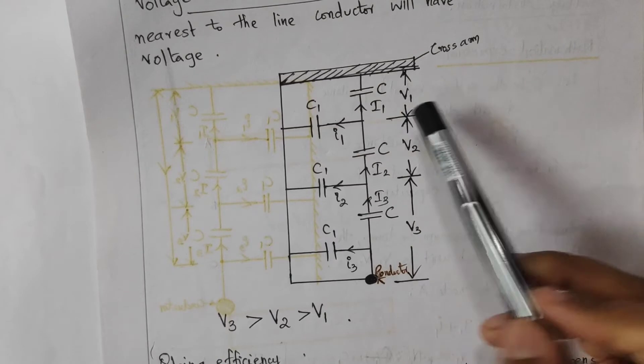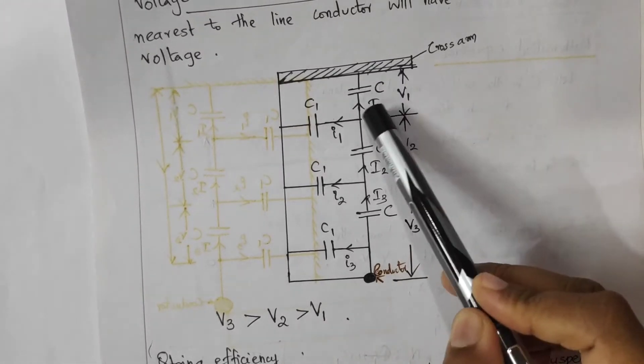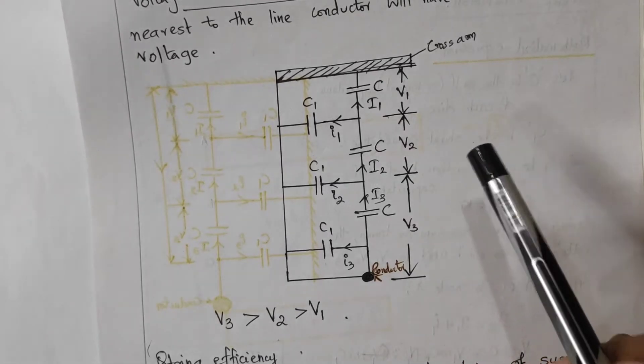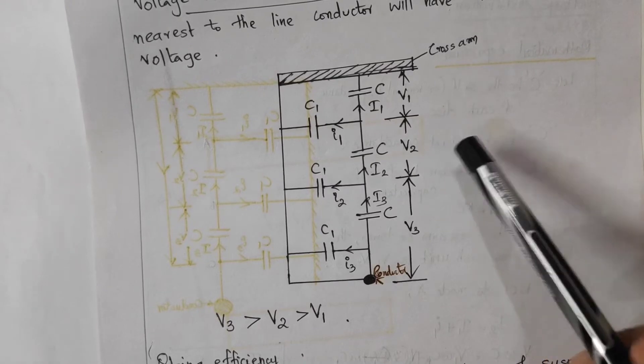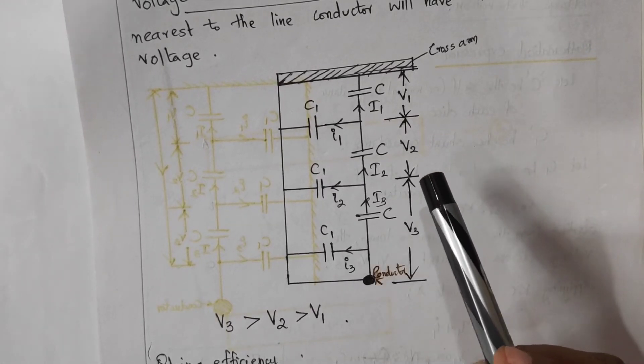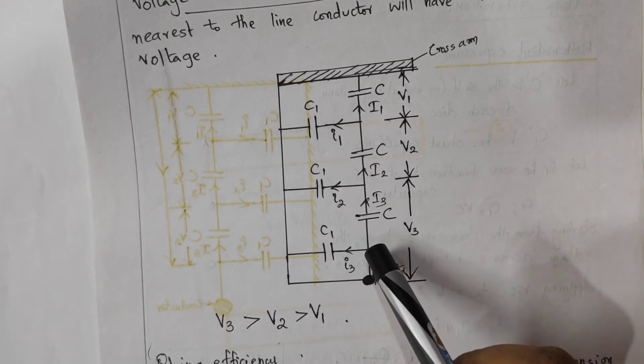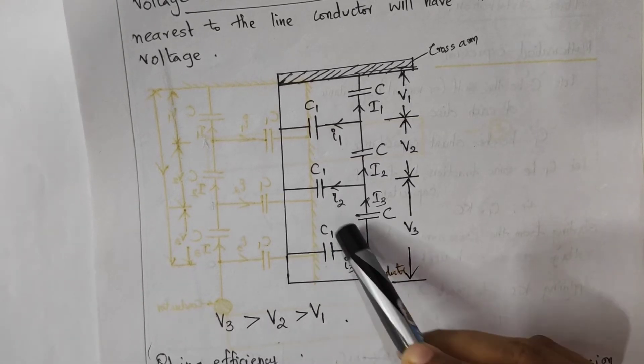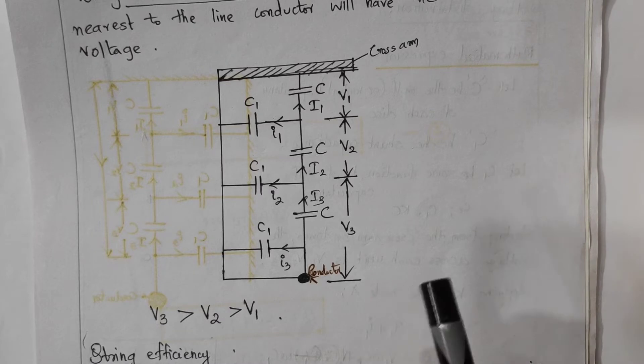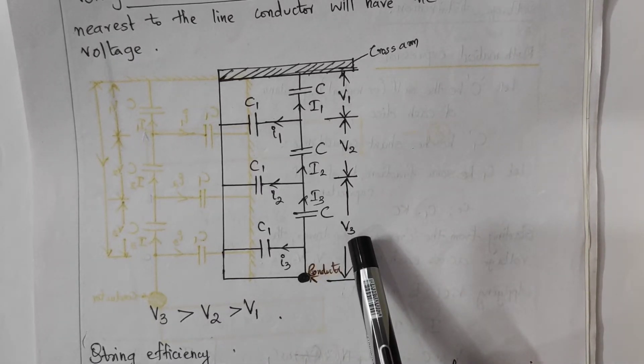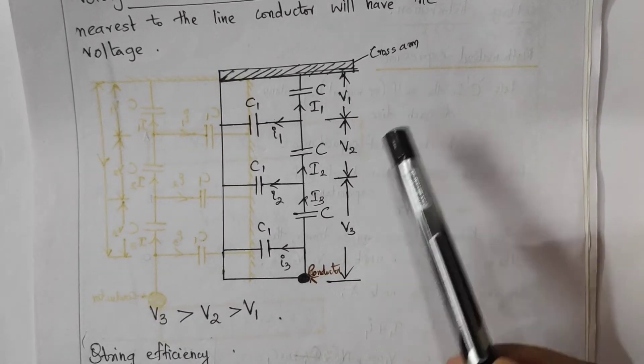In actual practice, the voltage across each mutual capacitance C will not be V by 3. The voltages will be different: V1, V2, and V3, and the total voltage of the string will be V1 plus V2 plus V3. The charging current will also be different through each mutual capacitance. The disc nearest to the line conductor will have the maximum voltage, so V3 is the maximum voltage, which is greater than V1.